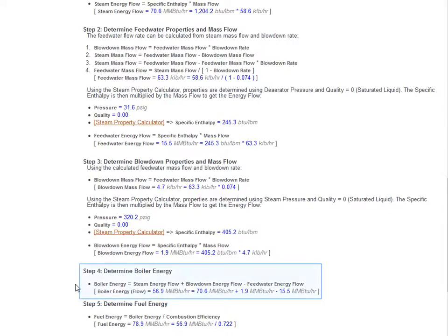The required boiler energy is then calculated as the difference between the feed water energy content and the combined energy content of the steam and blow down. The required fuel energy is then determined by using the combustion efficiency and required boiler energy.